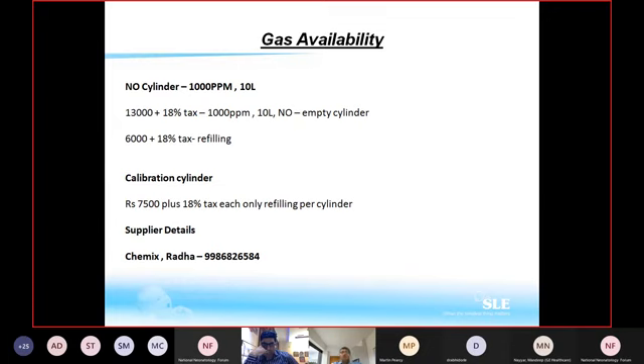And the suggestion is that because we don't want an empty cylinder during use, you probably need to buy 2-3 cylinders, depending on the usage, and always keep sending one of the cylinders to the supplier so that he can refill it and send it back, while you have at least 1 cylinder in use and 1 cylinder as a standby. So the recommendation is to have 3 cylinders. You need to plan that way.